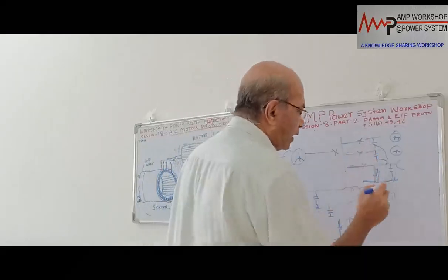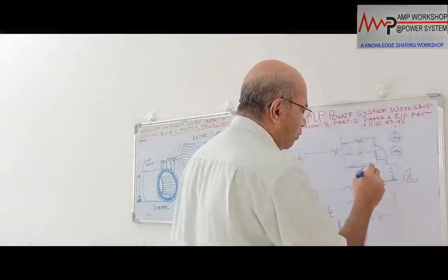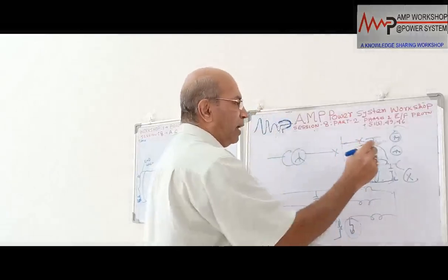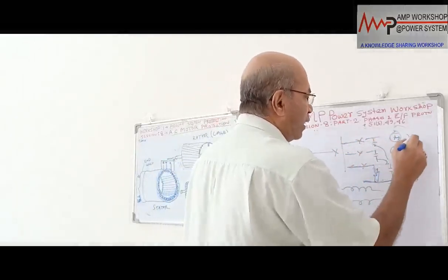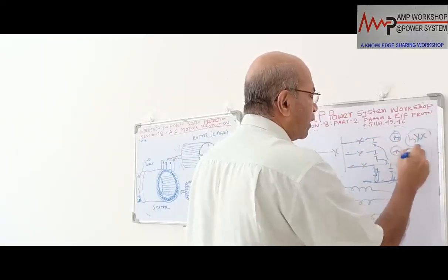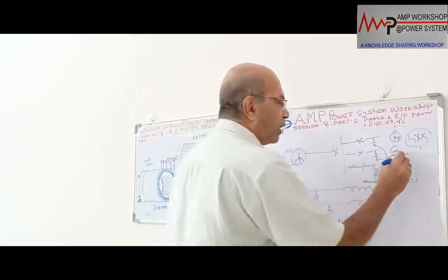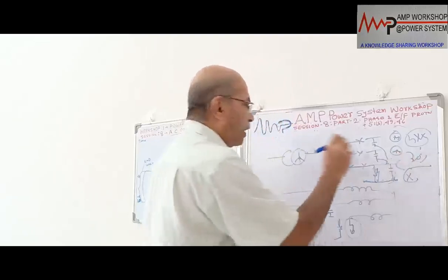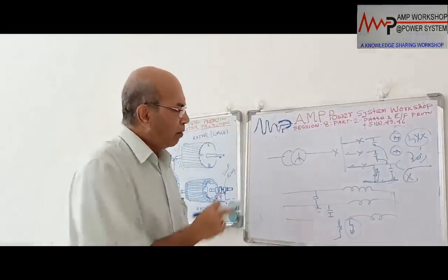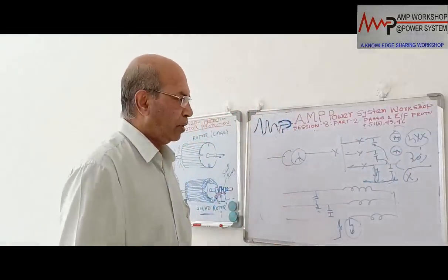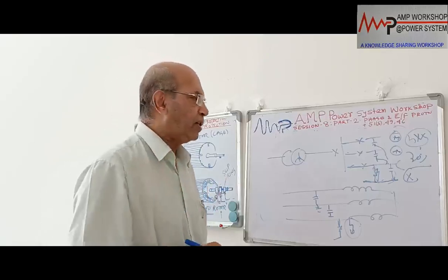Suppose the total charging current is X amount. During an earth fault condition, if there are n motors connected, then the total charging current is n times X, and we can provide the protection setting at about 30% of this charging current. In that way, in an unearthed system we can protect these motors. This is one of the ways, by measuring the charging current.